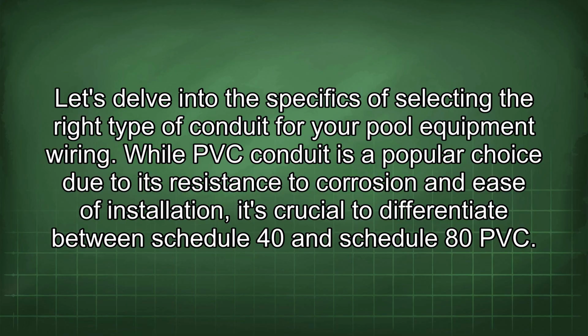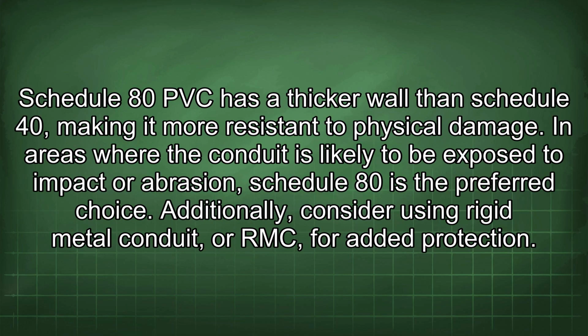While PVC conduit is a popular choice due to its resistance to corrosion and ease of installation, it's crucial to differentiate between Schedule 40 and Schedule 80 PVC. Schedule 80 PVC has a thicker wall than Schedule 40, making it more resistant to physical damage. In areas where the conduit is likely to be exposed to impact or abrasion, Schedule 80 is the preferred choice. Additionally, consider using rigid metal conduit, or RMC, for added protection.